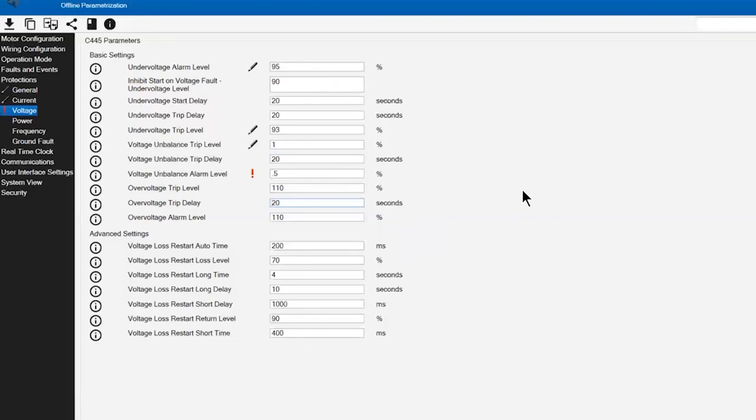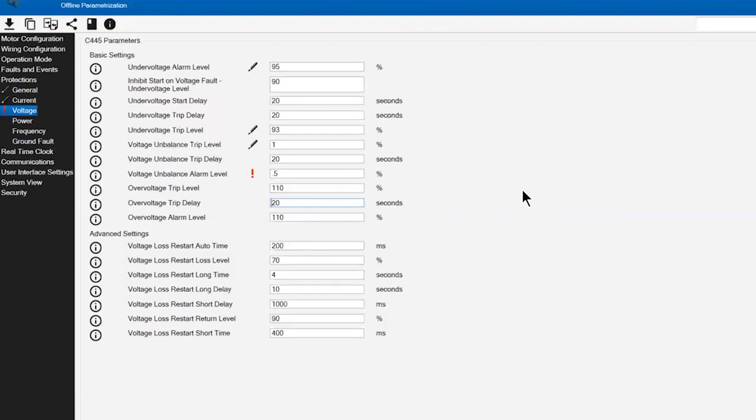Based on the protections that I have set, they cover a wide range of faults. Some of them that we discussed were loose connections, early warning winding failures, problems with voltage being supplied through the distribution system, and the effects on the motors. So these are some easy ways to really enhance that.